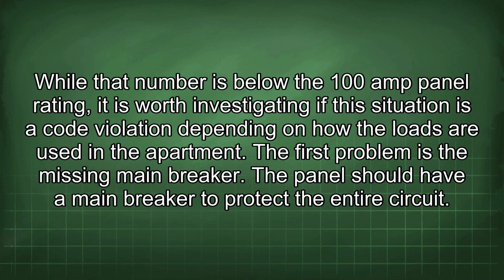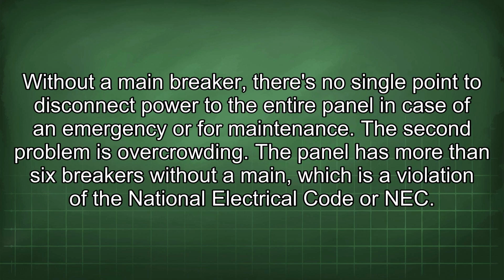The first problem is the missing main breaker. The panel should have a main breaker to protect the entire circuit. Without a main breaker, there's no single point to disconnect power to the entire panel in case of an emergency or for maintenance. The second problem is overcrowding.